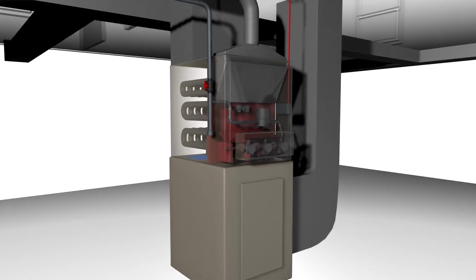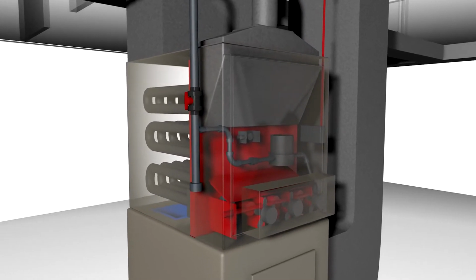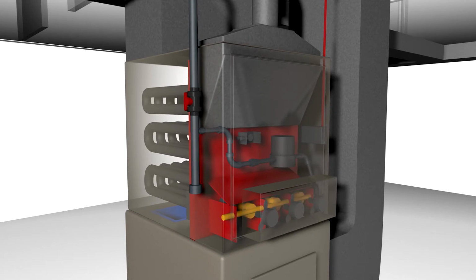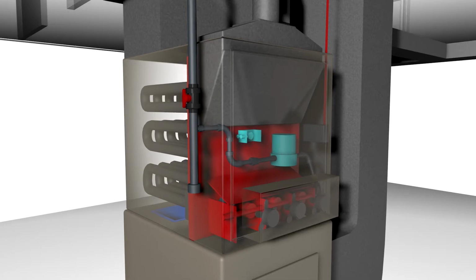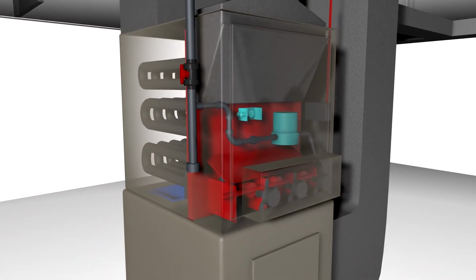The burners in your furnace are similar to the burners on a gas grill. They're a set of tubes through which the natural gas enters the furnace and is burned. The flames are initiated and controlled by an igniter, the gas valve, and flame sensors. Depending on the age or model of your unit, you may have a pilot light, a small gas-powered flame that stays constantly lit to ignite the burners on demand, or you may have an electronic ignition system. The flame sensor is a safeguard that shuts off the gas if the burners for some reason do not ignite.